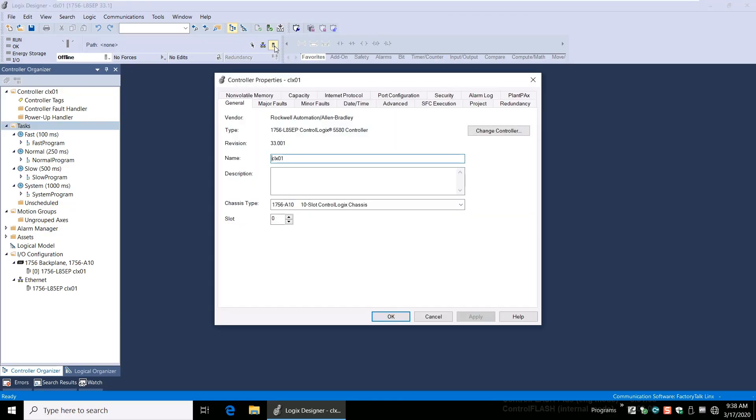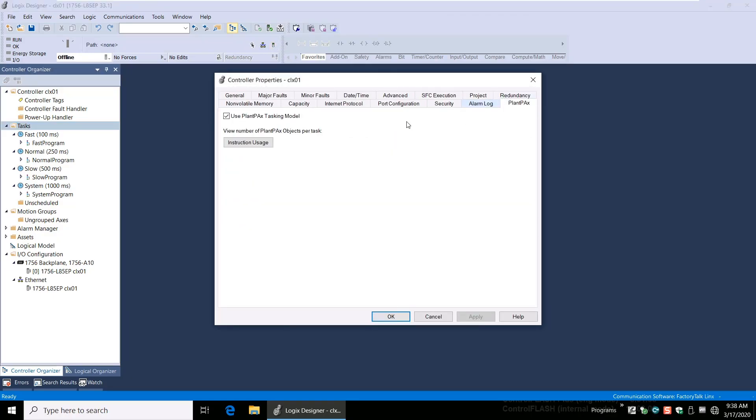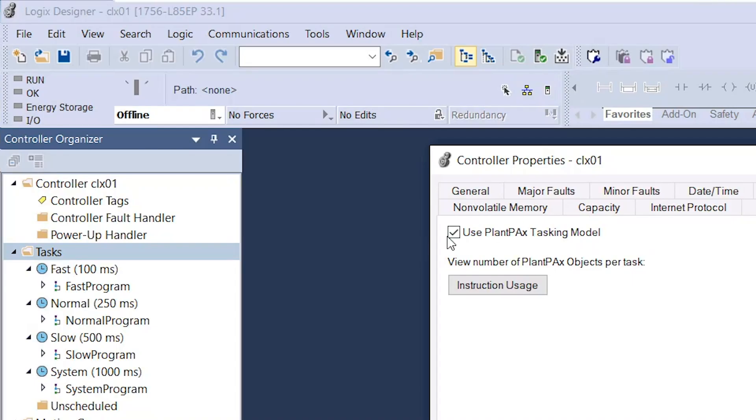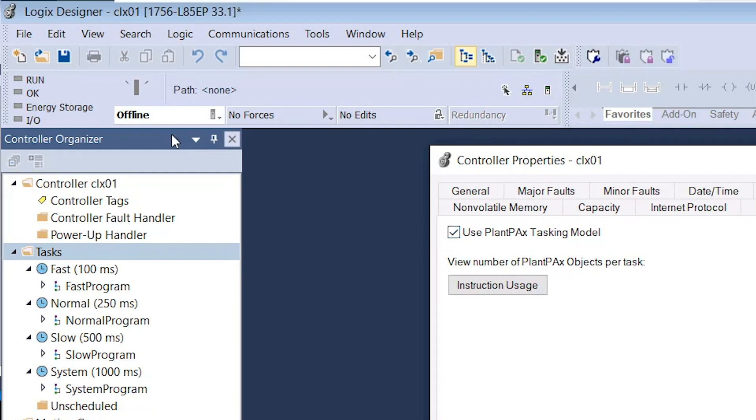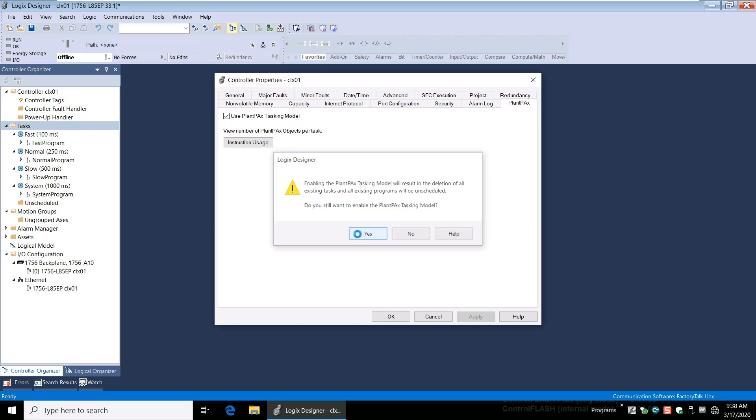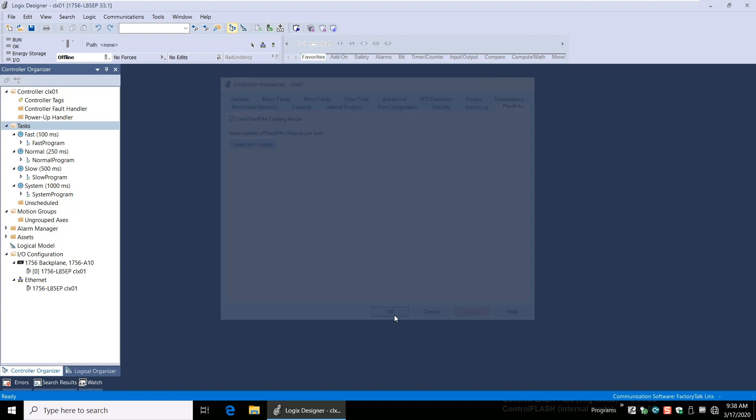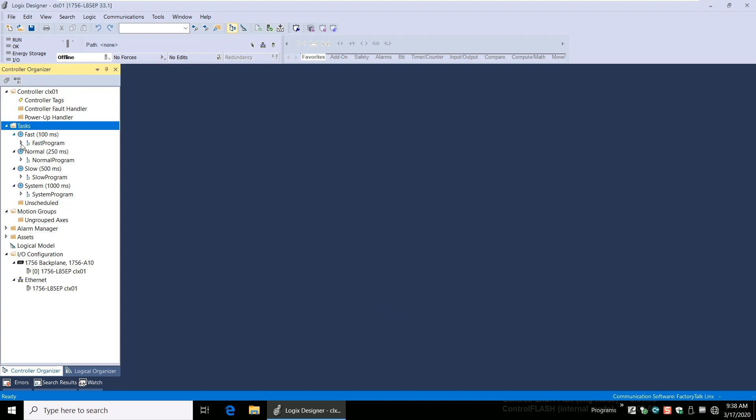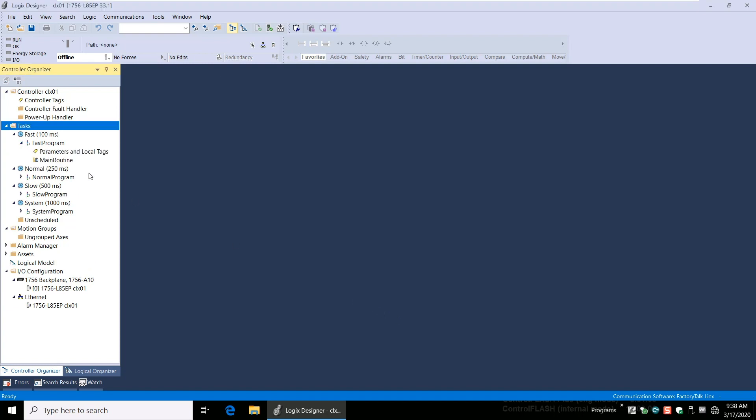A few other things to be aware of. The task model cannot be changed online once selected. If Use PlantPAX tasking model is selected, one cannot add or remove tasks, nor can the task priorities be changed. Only the task periods and watchdog timers in Task Properties can be modified when PlantPAX task model is selected.